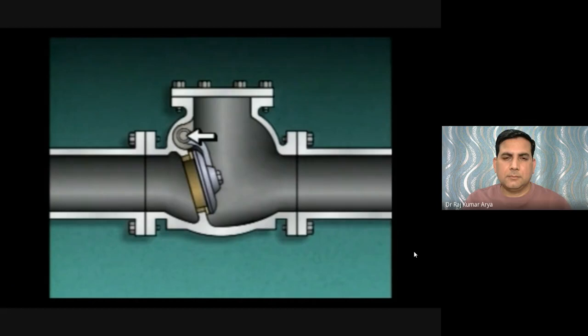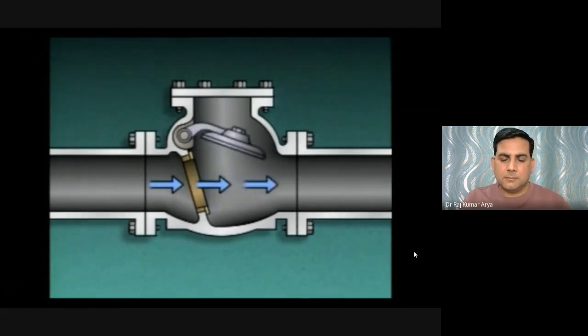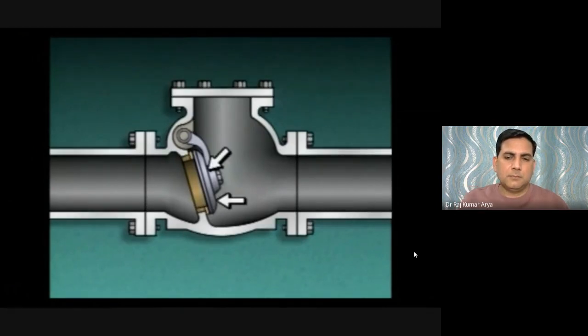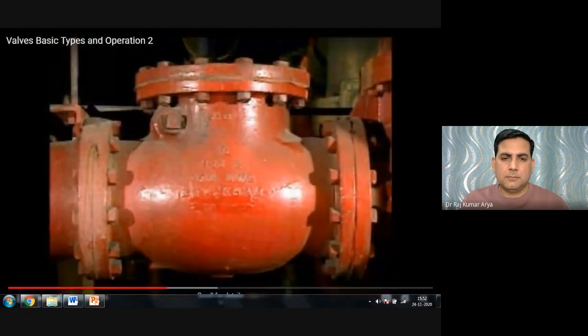The disc is hinged at the top of the valve body by the arm, with the pivot pin allowing the disc to hang in place and close against the seat to block fluid flow. When pressure acts on the disc, it pivots or swings away from the seat, opening the valve and allowing flow. When flow stops, gravity pulls the disc onto the seat. Back flow pressure then pushes the disc firmly against the seat to fully close the valve. Flow direction is usually indicated by an arrow cast into the valve body.